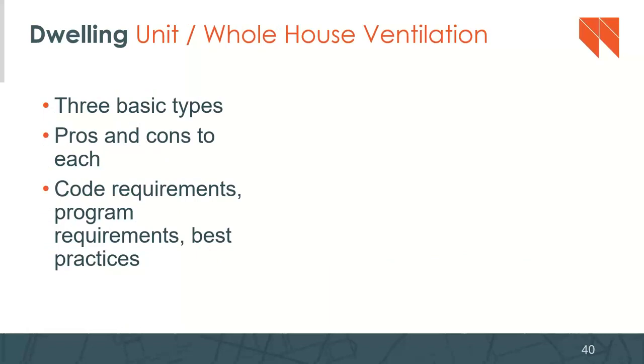Okay, there are a couple of different types of whole house ventilation. We're going to talk about the three basic types, the pros and cons, and hopefully address the code requirements, the program requirements, and then best practices. So let's get on with it. Exhaust only. Exhaust only is moving air from the inside to the outside, and that's it. We just got done talking about a whole bunch of different exhaust strategies. In the context of whole house ventilation, you have the option to do an exhaust only strategy. That ventilation system is usually running all the time, or periodically throughout the day on a timer, but it is pulling air out.